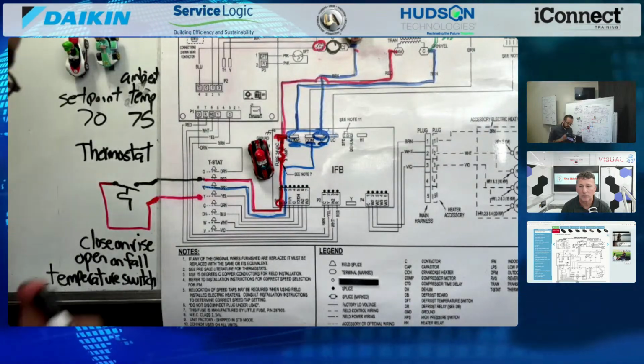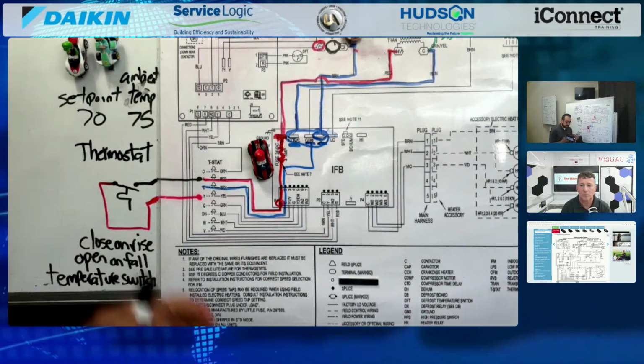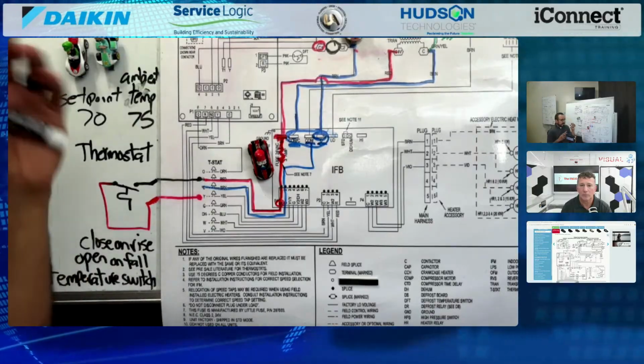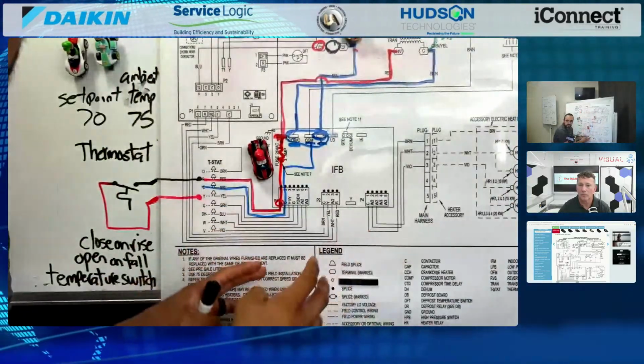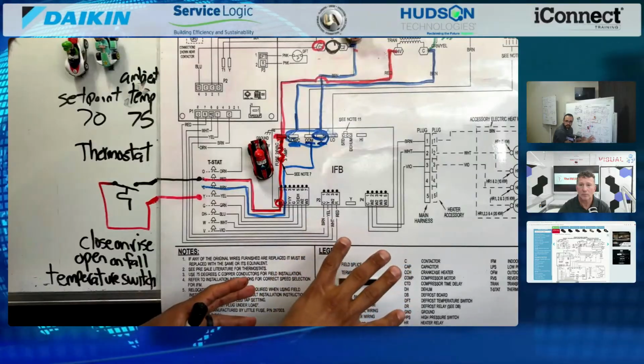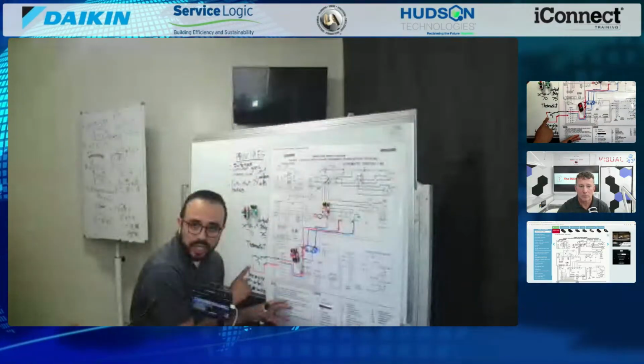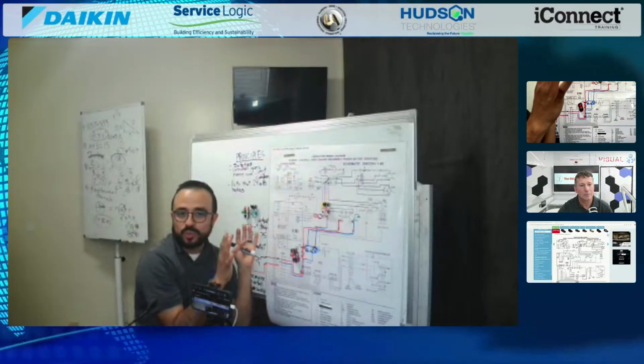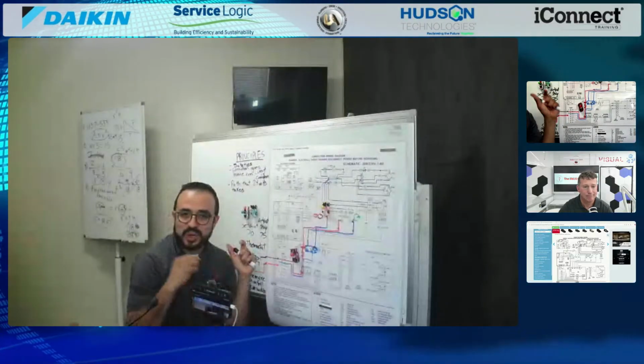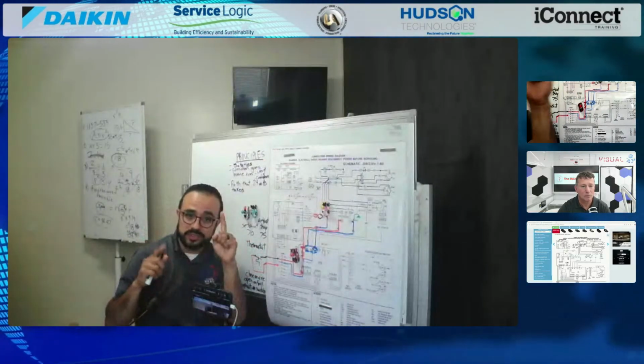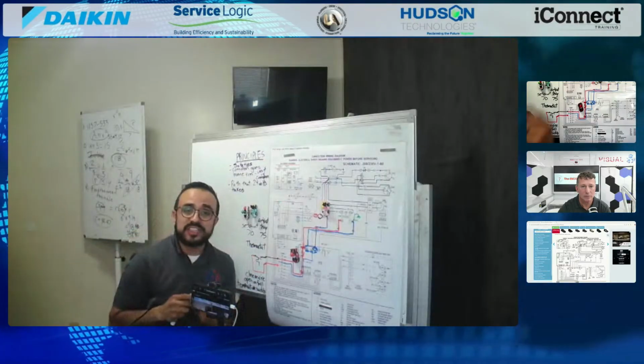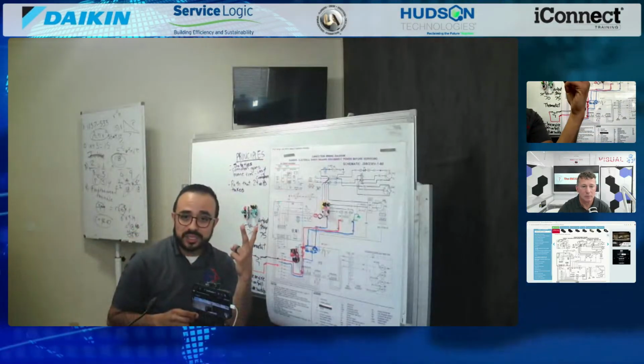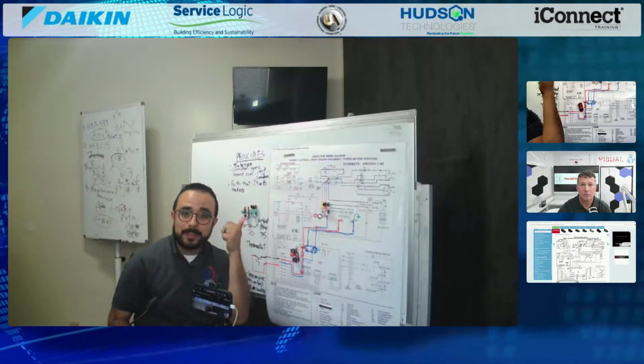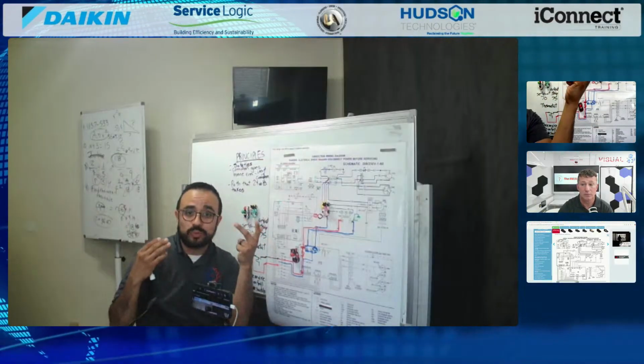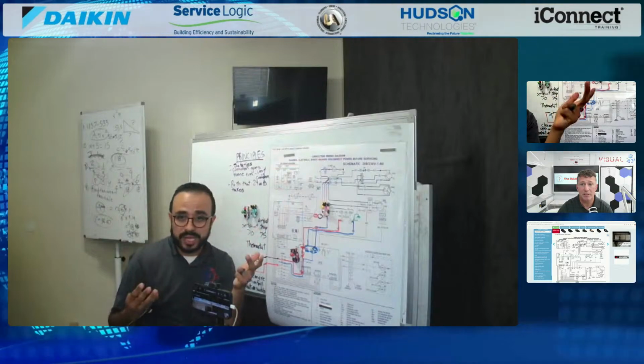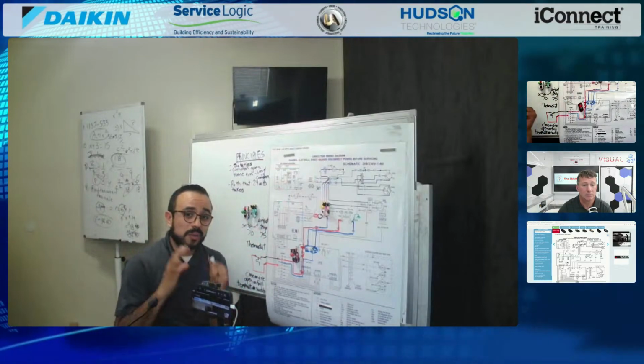This is where students must understand, and instructors as well, that all this can be beautifully wired for you, it can be made out of gold, but if your thermostat doesn't work, it doesn't matter. Nothing's going to work. Your thermostat has to be wired correctly. It's got to be programmed correctly, because it can be wired wrong, and it can be a bad thermostat head. I've even seen bad thermostat back plates. Absolutely, the basis can be bad.